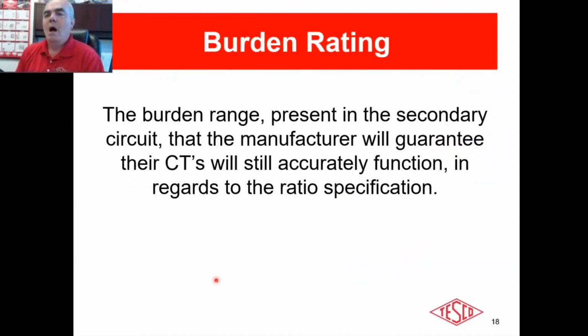Okay. The burden range. All right. So why are transformers given an accuracy reading with a burden? Because theoretically, there should be no burden. But once again, we don't work in a theoretical world. We don't work in an ideal world. There are burdens. How do we create a burden on a setup? Well, the amount of wire that we have between the transformers, the test switch, the meter, that length of wire and diameter of wire, that puts a certain burden on the service, okay?